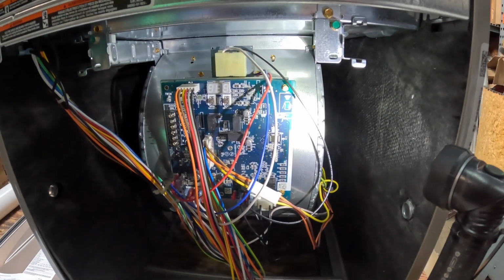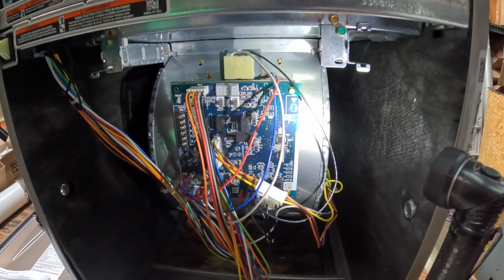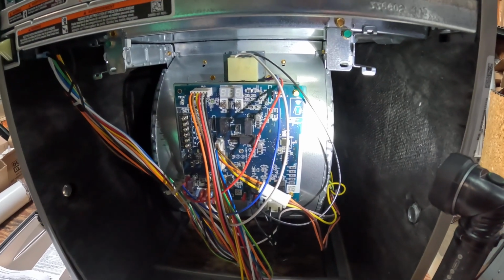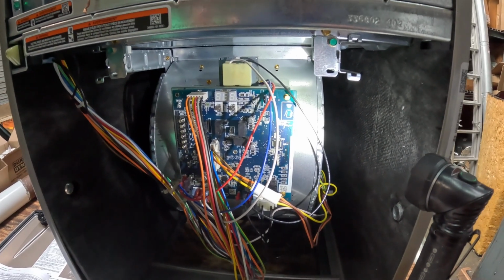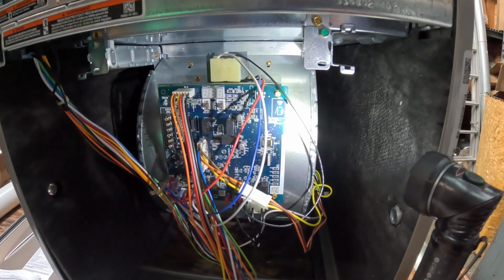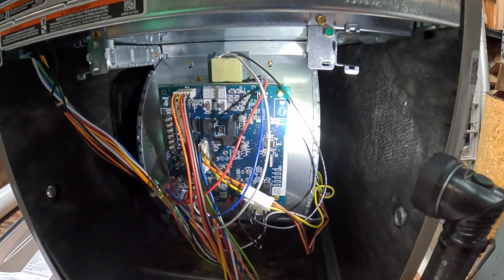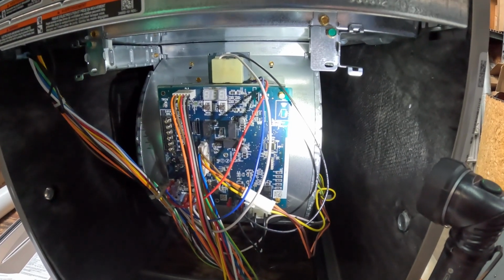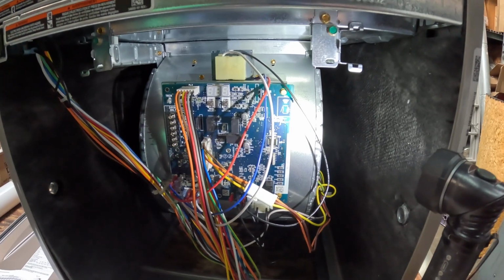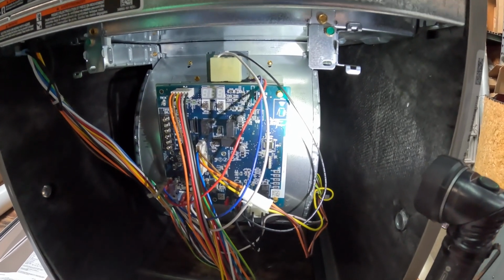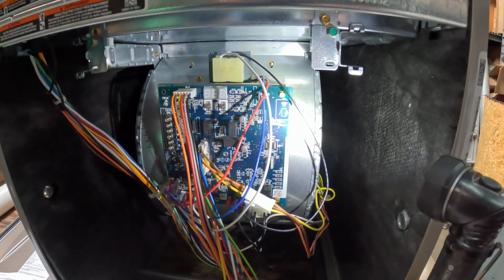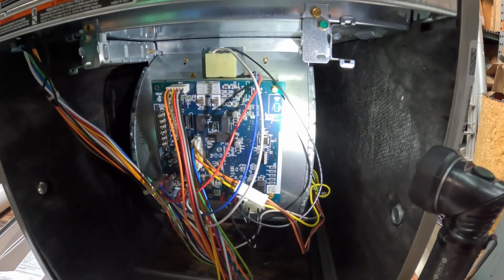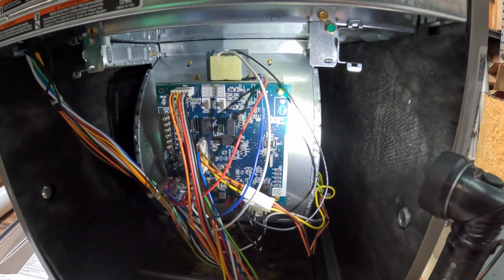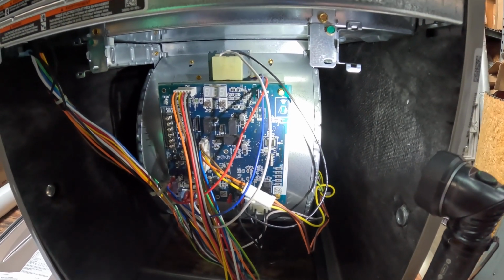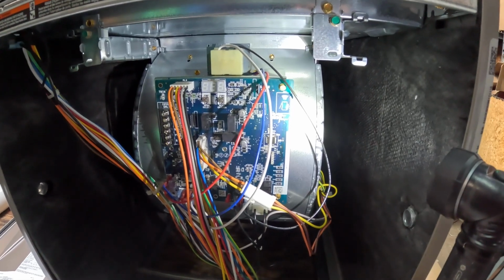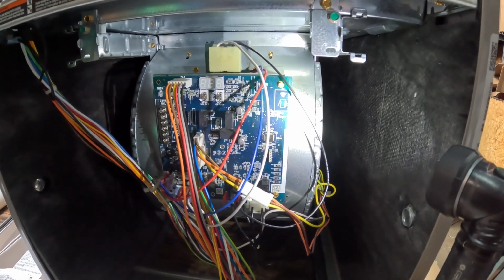I am at my shop right now. This is a training furnace that we're using, so we can get up to speed on how this works. So I'm going to connect to this with my smartphone. I'm going to show you how you can program this board. That way, when you're out in the field or at your shop before you go to the job, you know how to do this. You do need to do this on every furnace. This is a 60,000 BTU furnace, so it's basically a 4-ton furnace. I'm going to show you how to program it and the steps that you take to do that.